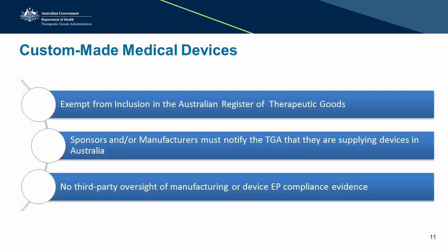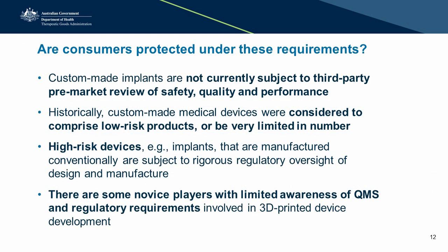Now, custom-made devices, as I've mentioned, are not required to be included in the ARTG, so there's no pre-market assessment of these products. The only requirement is that sponsors in Australia or sponsors of overseas manufacturers or in Australia manufacturers must notify the TGA that they're supplying custom-made devices. So there's no third-party oversight of the evidence of quality, safety, and performance or of the manufacturing. So are consumers protected under these requirements?